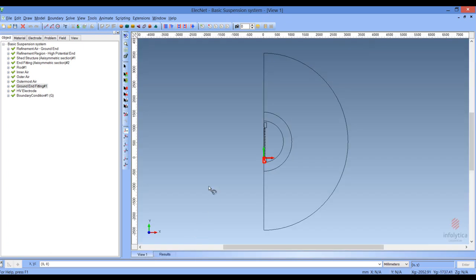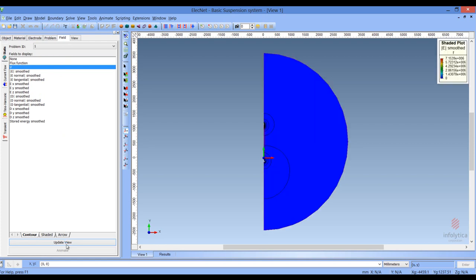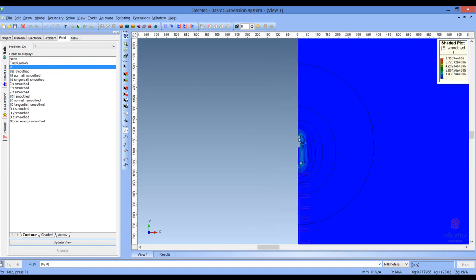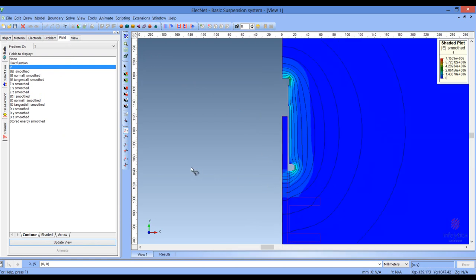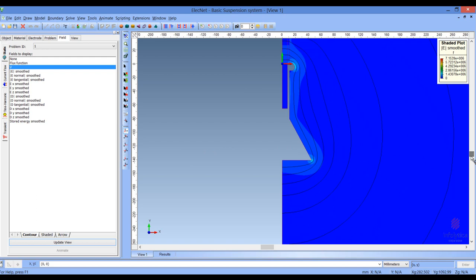Now let's look at what the fields look like. Going to the field tab and updating the view, we'll see our default field structure. First, let's have a look at the top around the energized end. You can see how the distribution of the electric field stress is highlighted in color, and the equipotential lines which are the lines shown here. Panning down to the bottom we can also see what the electric field stress is around the ground structure.